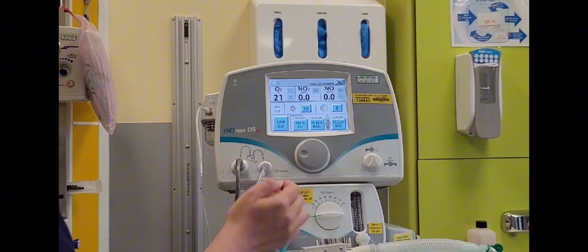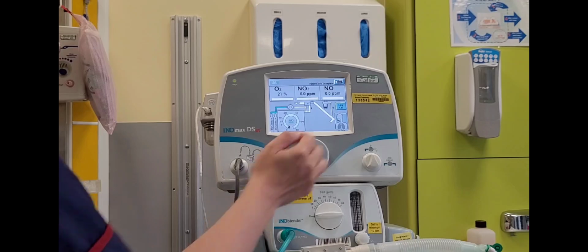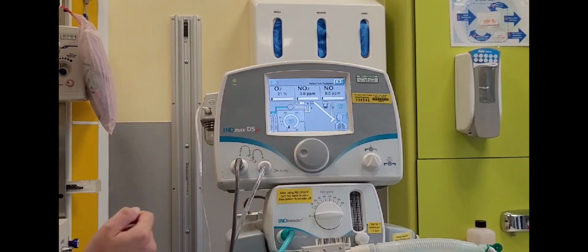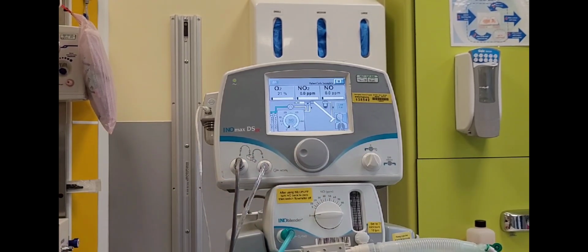To perform the low range calibration, select the menu button, press local and press local again. You need to wait for all the bars to turn green. This can take up to 5 minutes. Occasionally they will not turn green and the calibration has failed.